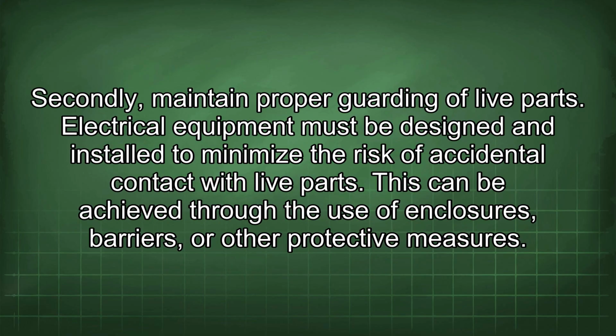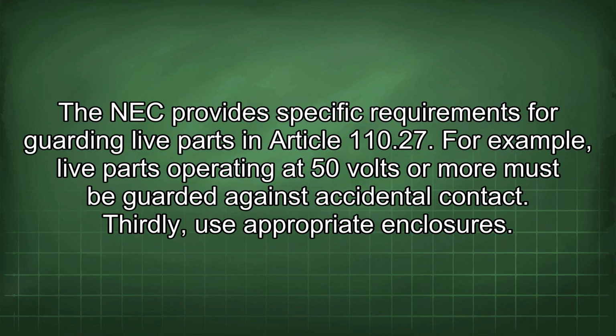Secondly, maintain proper guarding of live parts. Electrical equipment must be designed and installed to minimize the risk of accidental contact with live parts. This can be achieved through the use of enclosures, barriers, or other protective measures. The NEC provides specific requirements for guarding live parts in Article 110.27. For example, live parts operating at 50 volts or more must be guarded against accidental contact.